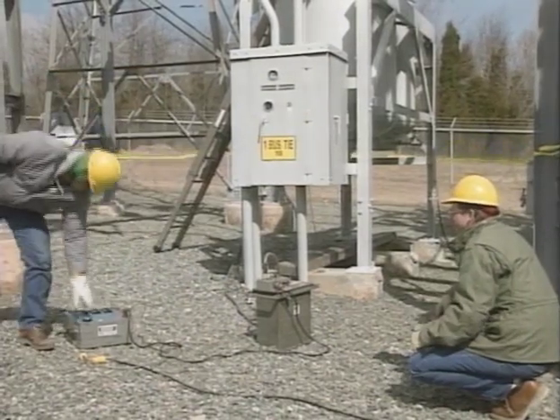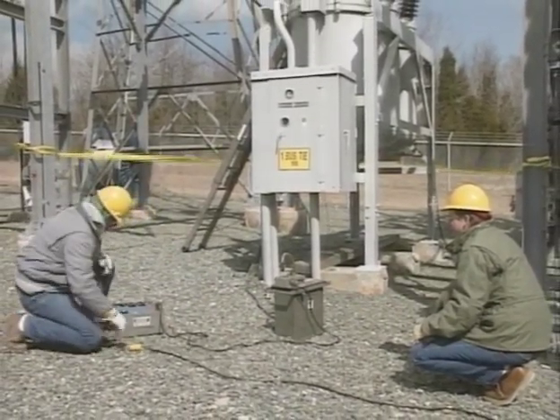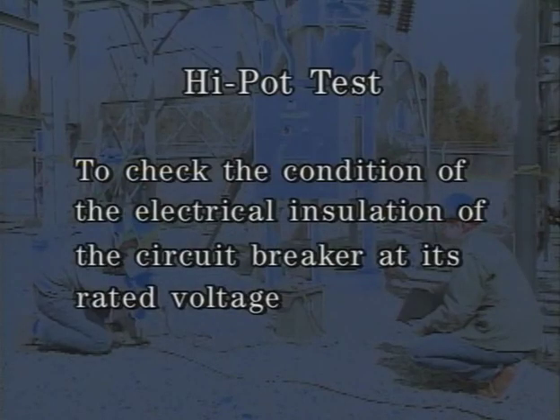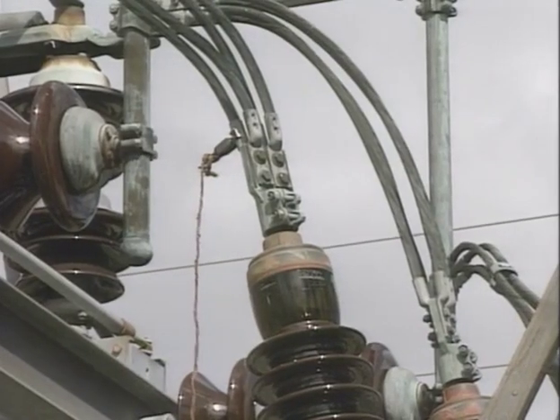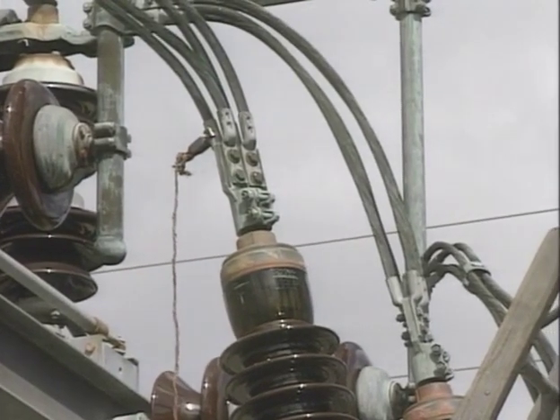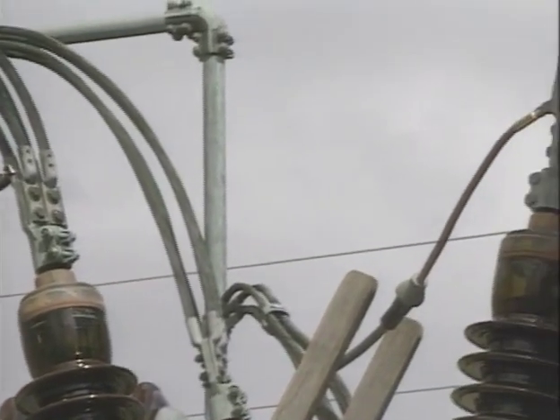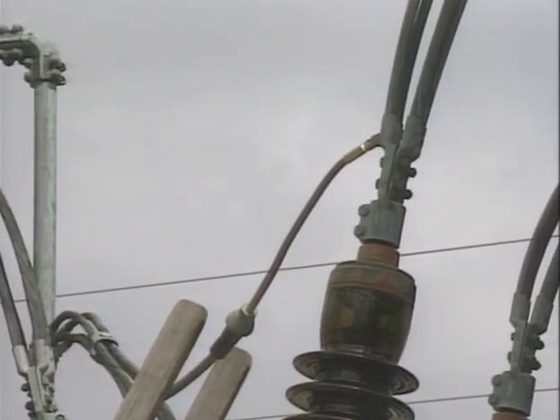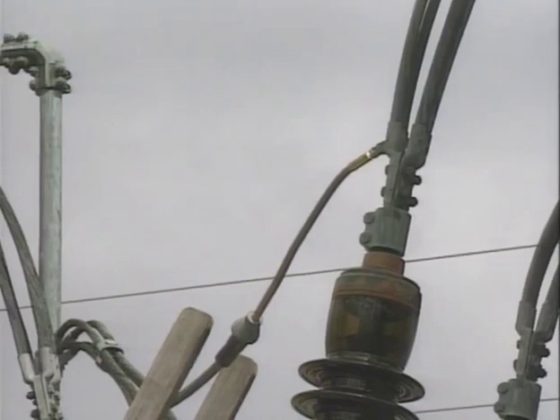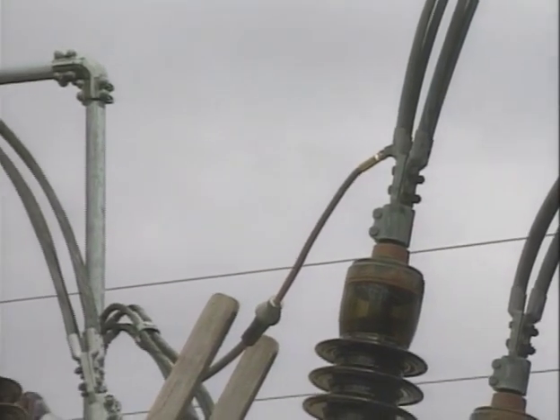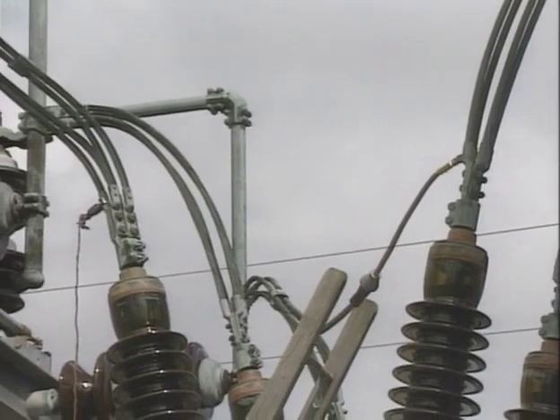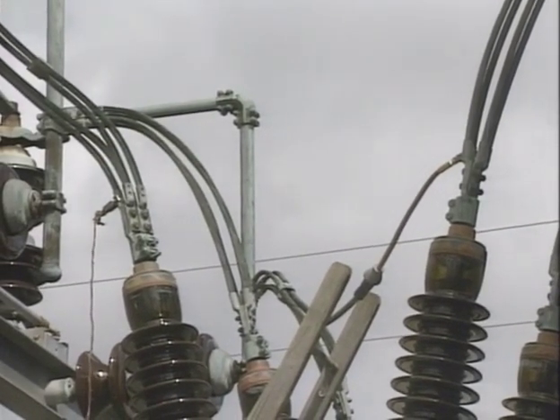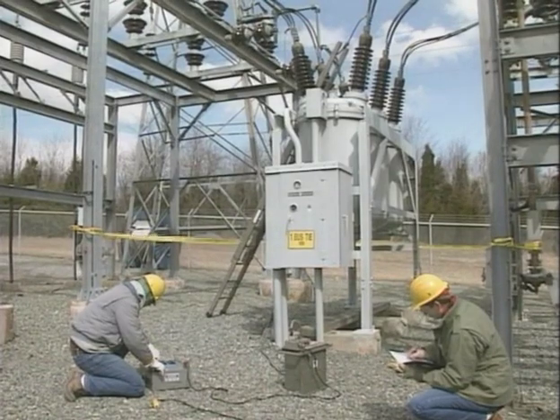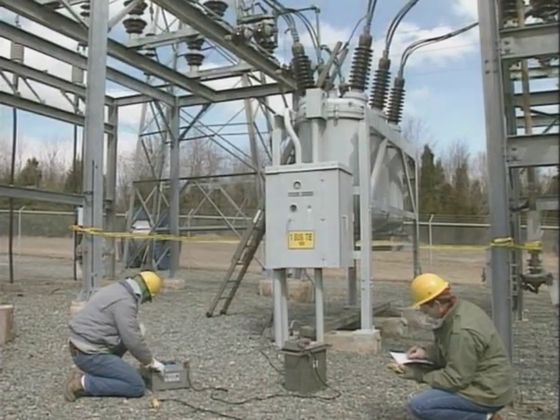A fifth proof test that sometimes is performed on a circuit breaker is the high pot test. The purpose of a circuit breaker high pot test is to check the condition of the electrical insulation of the circuit breaker at its rated voltage. In principle, the test is performed by applying rated AC or DC voltage across the breaker bushing terminals. With the breaker contacts open, leakage current is measured across the open contacts in both directions. With the contacts closed, leakage current is measured across the closed circuit to ground. The test instrument indicates the applied voltage and measures and indicates any leakage current.